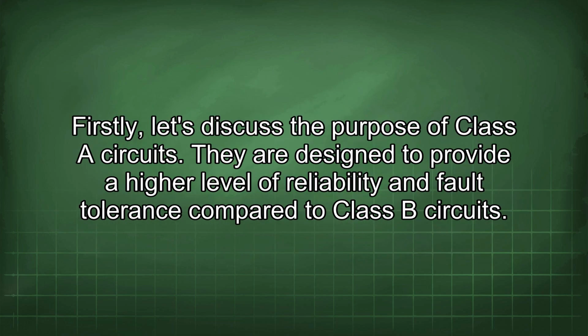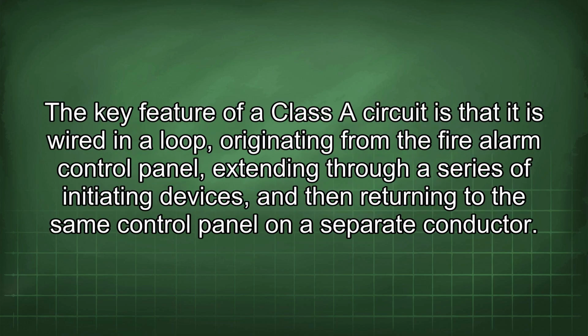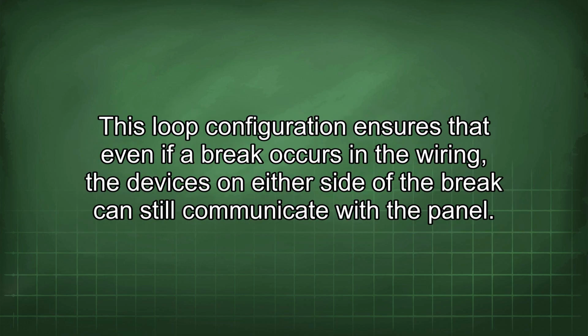Firstly, let's discuss the purpose of Class A circuits. They are designed to provide a higher level of reliability and fault tolerance compared to Class B circuits. The key feature of a Class A circuit is that it is wired in a loop, originating from the fire alarm control panel, extending through a series of initiating devices, and then returning to the same control panel on a separate conductor. This loop configuration ensures that even if a break occurs in the wiring, the devices on either side of the break can still communicate with the panel.